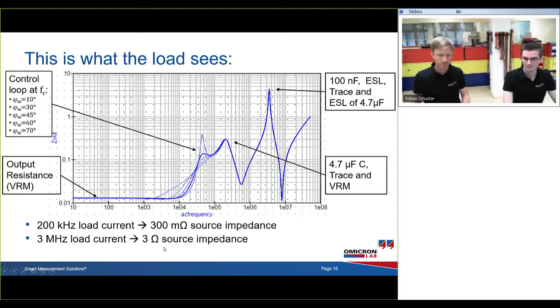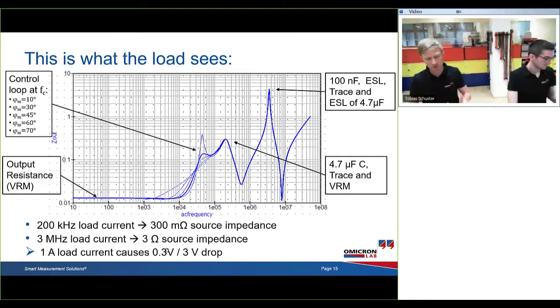And at a 3 megahertz load, if there is 3 megahertz content in the current, then 1, 2, 3, at 3 megahertz we are nearly at 3 ohms, or at 3.5 megahertz, something like that. So there is a factor of 10 in between, and at frequencies below 10 kilohertz we are at 30 milliohms and lower. This means that if the 200 kilohertz load current, for example, has 1 amp, then it causes either a 0.3 volt, or 300 millivolts, drop at 200 kilohertz, or even a 3 volt drop at 3 megahertz. So practically at 3 megahertz, this system won't be able to deliver 1 amp transient currents that have 3 megahertz transient content. Also for 200 kilohertz, there will be a significant voltage drop. For slower transients, of course, it's not such a problem anymore.